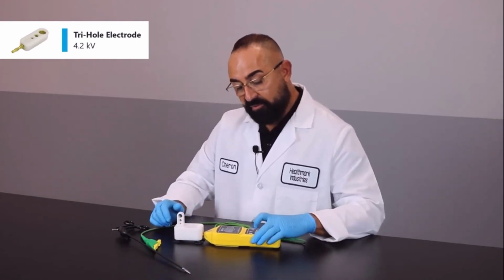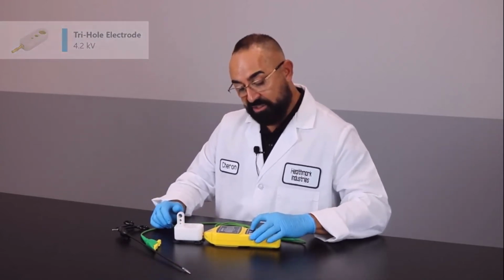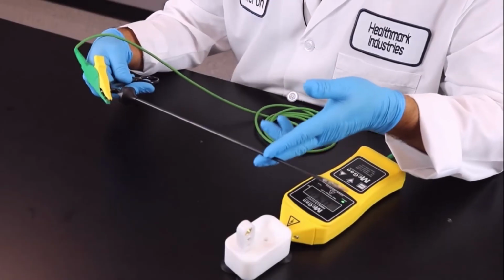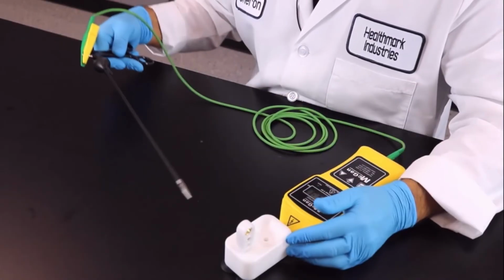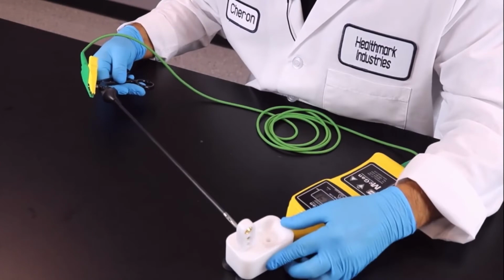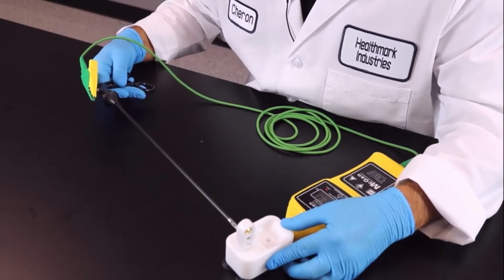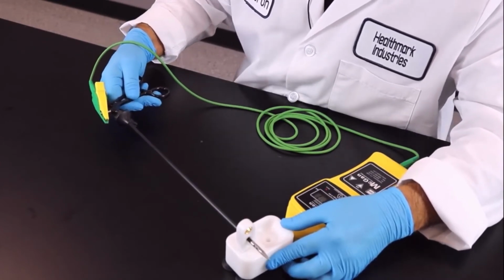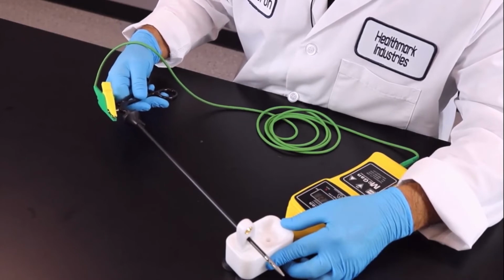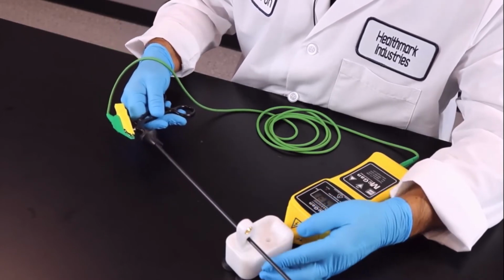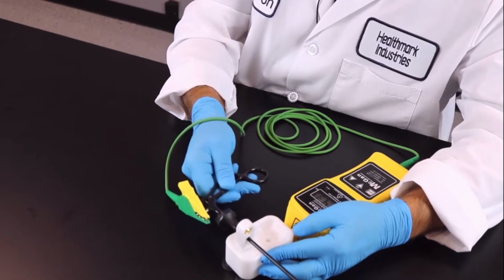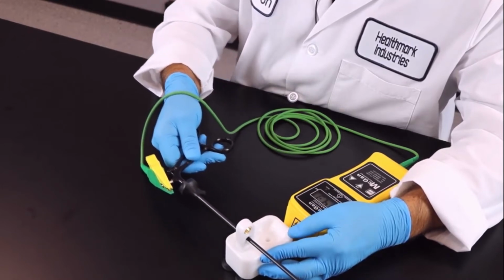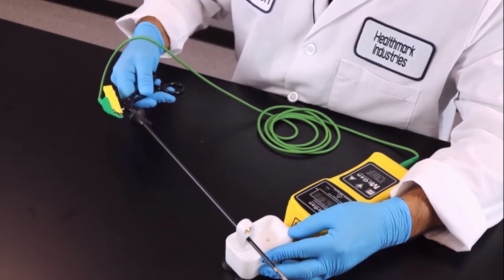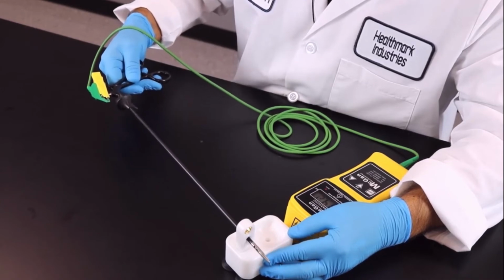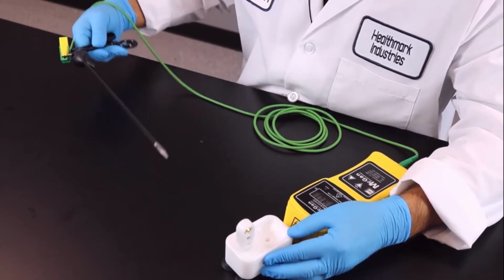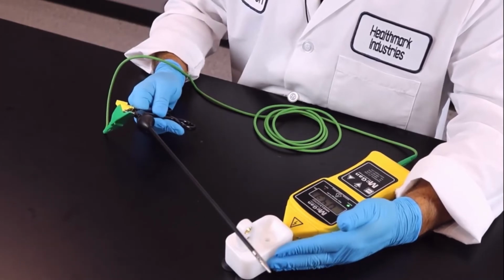You're going to set this voltage setting at 4.2. Because this instrument is 5 millimeter in diameter, you'll be using the middle hole, like you see here, tested to make sure it's grounded. You want to make sure you're going slow. And there's a break in this particular laparoscopic instrument. Go all the way to proximal end, go all the way back slowly to distal, and of course there is a break there, and that's how you test with that accessory.